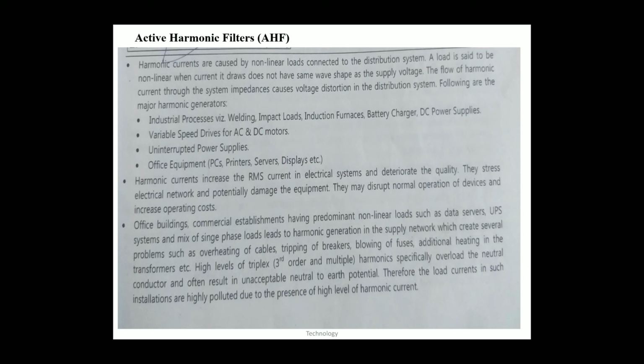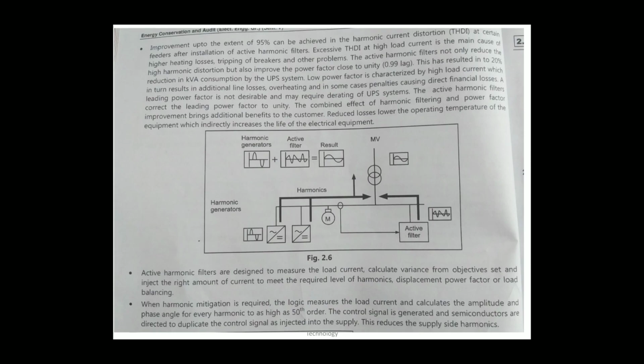High levels of triplen, that is third order and multiples of harmonics, especially overload the neutral conductor and often result in unacceptable neutral to earth potential. Therefore, the load currents in such installations are highly polluted due to the presence of high levels of harmonic current. Improvement of up to 95% can be achieved in the harmonic current distortion at certain feeders after installation of active harmonic filters.